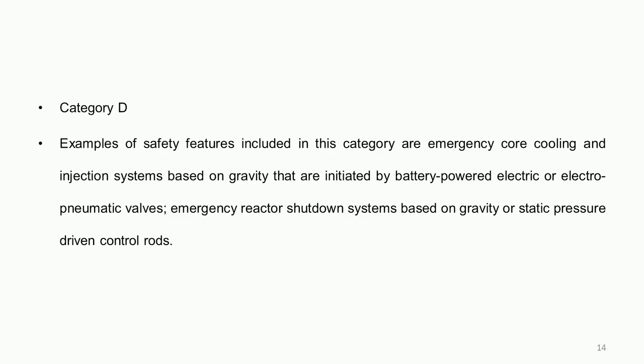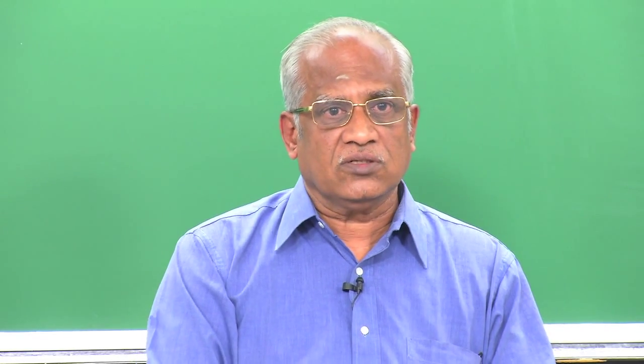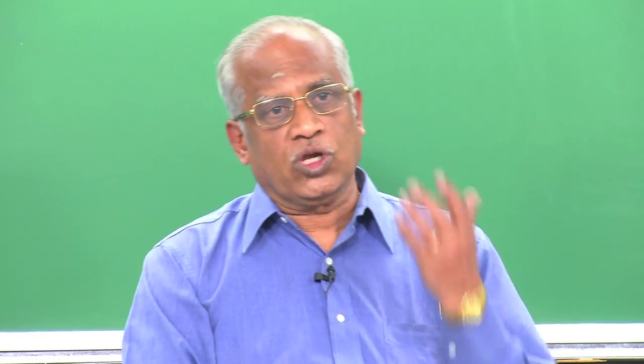Category D, the least passive, essentially includes battery-powered electric or electro-pneumatic valves, or emergency shutdown systems based on control rod drives falling under gravity — but they do require a signal for actuation, which is the major distinguishing factor.